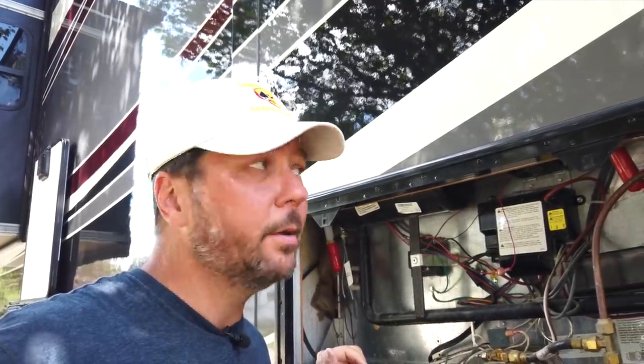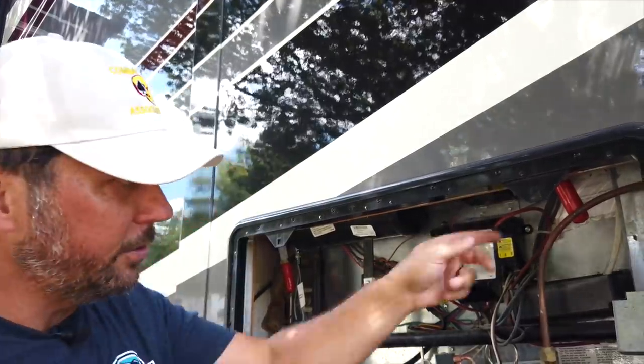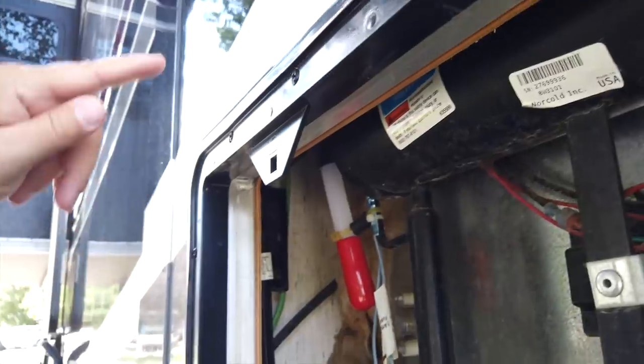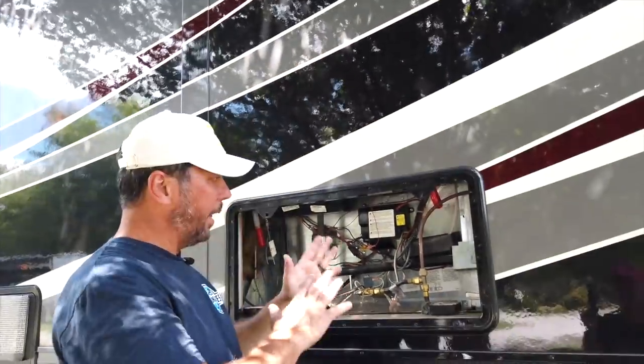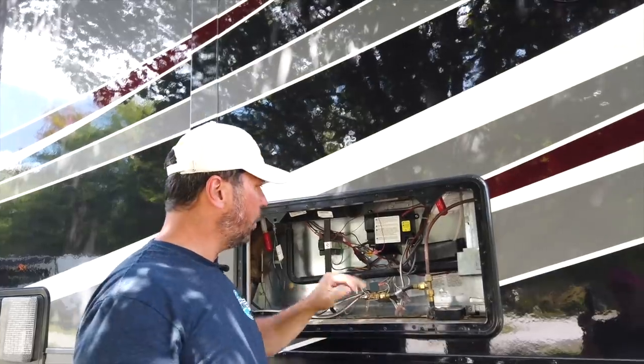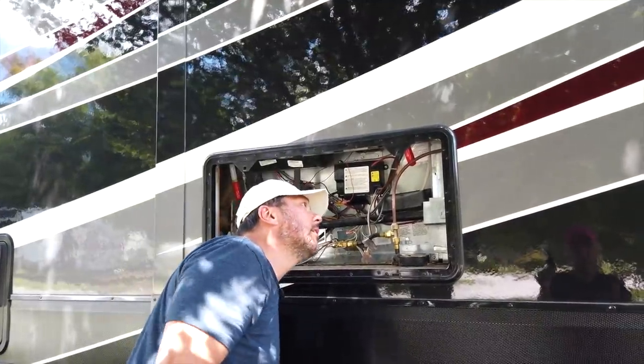I think if it were a little bit tighter, it would be good. If we didn't have our fire suppression system installed, I would do that. You can see these red caps here and here. That is a fire suppression tube that wraps up and around in there. And that's kind of blocking airflow too, which is good, making it go through. I just want to clean it up down here. Other than that, there's just not a whole lot for us to do in here.